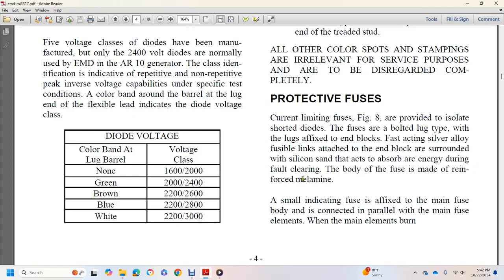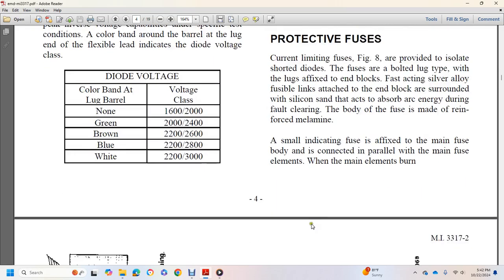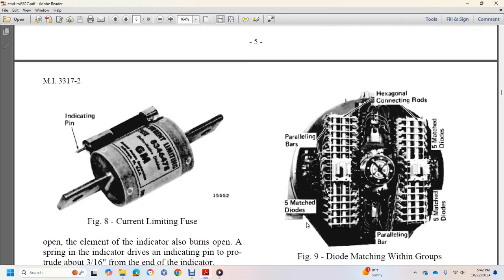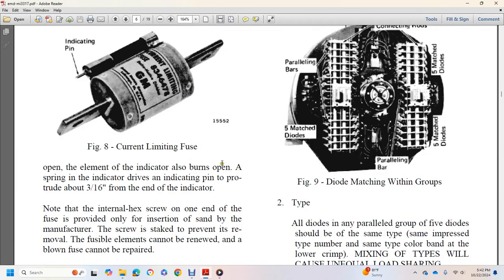The body of the fuse is made of reinforced melamine. A small indicating fuse is connected in parallel with the main fuse element. When the main element burns open, the indicator element burns open, and a spring drives the indicating pin to protrude 3/16 of an inch from the end of the indicator.